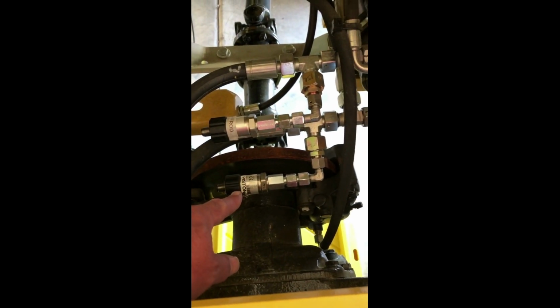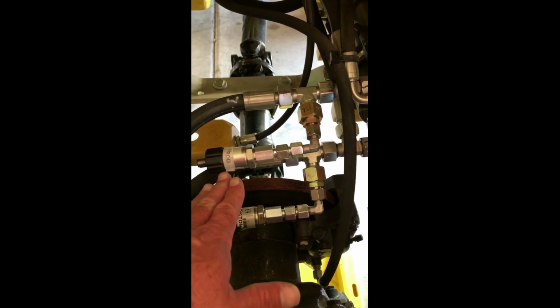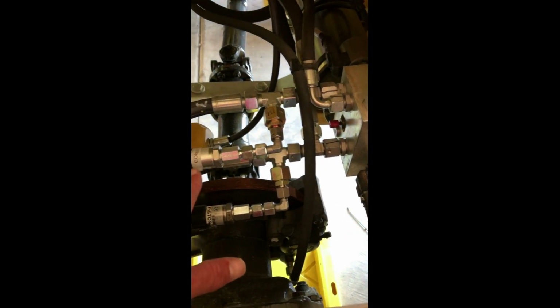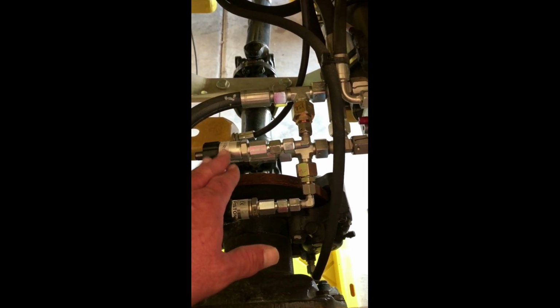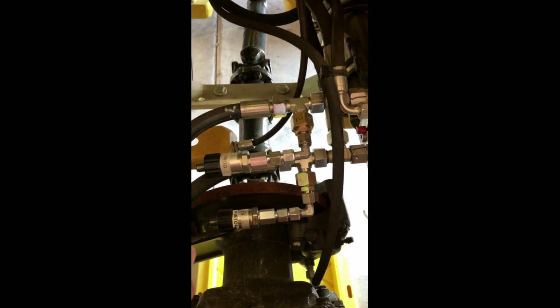Here is a shot of the pressure transducers. I traced the lines from the one cylinder on this machine down to where it comes out of the valve here, and installed T's. You can see this one's labeled piston, so that will go to the back end of the lift cylinder, and the other one here marked rod, that goes up to the rod end out here. Also, try to install your sensors where the end of the sensor is kind of running uphill. That will allow any air that might be trapped in the sensor to hopefully escape and go back through the system and out into the tank.